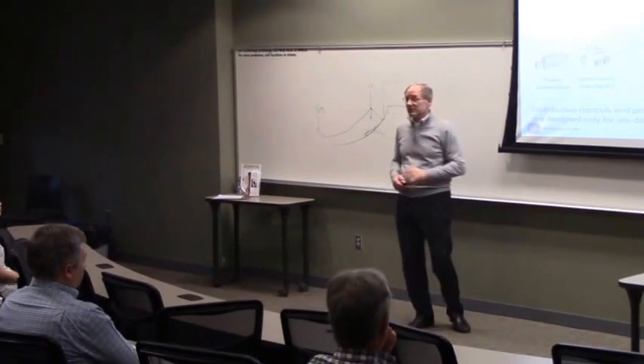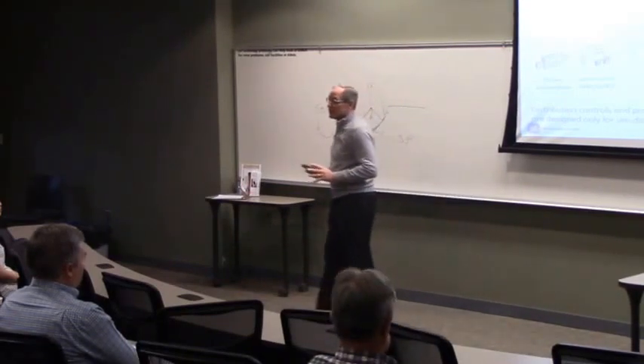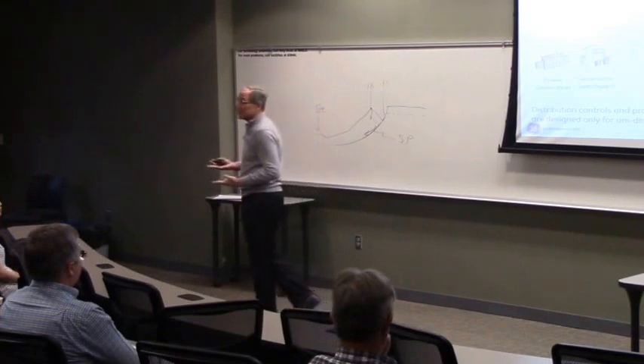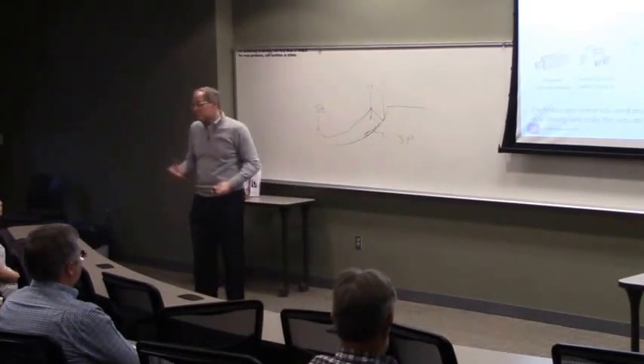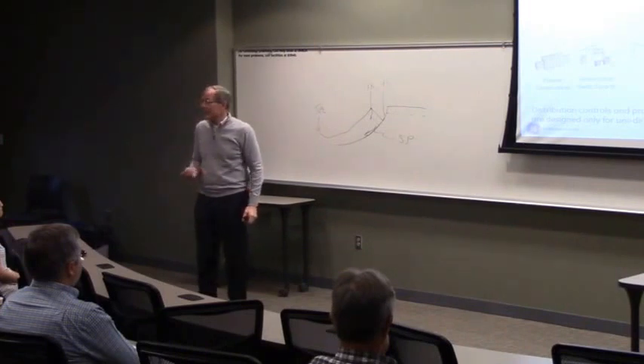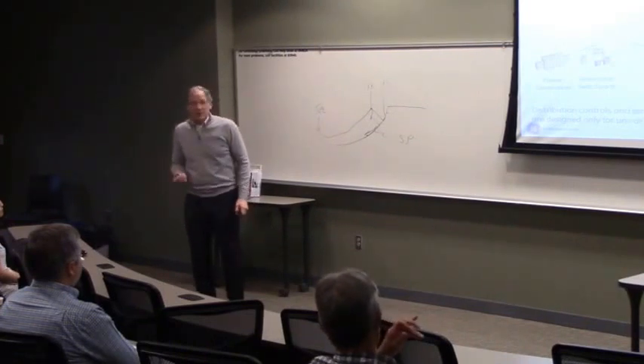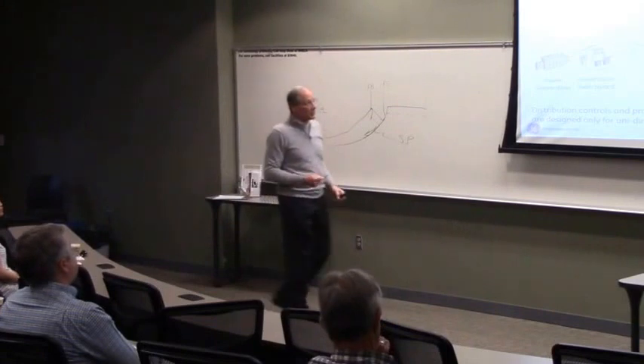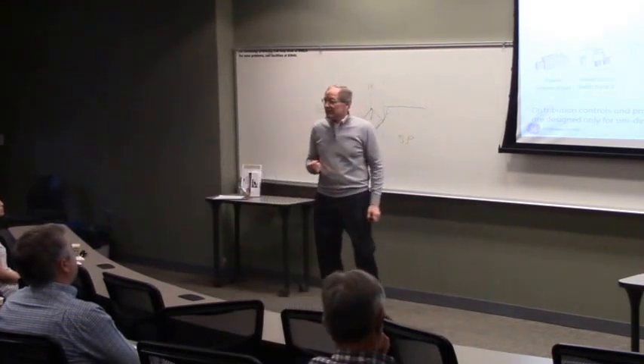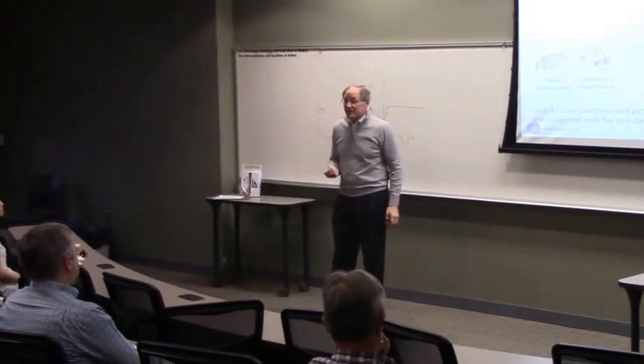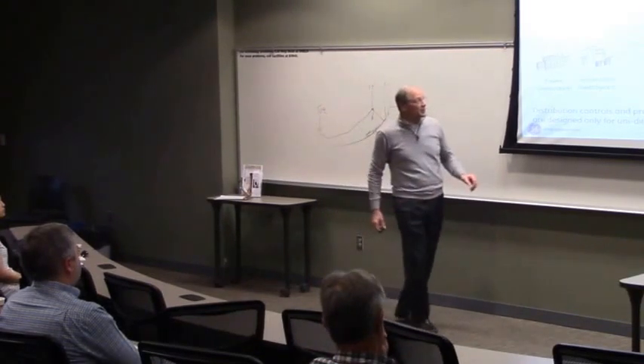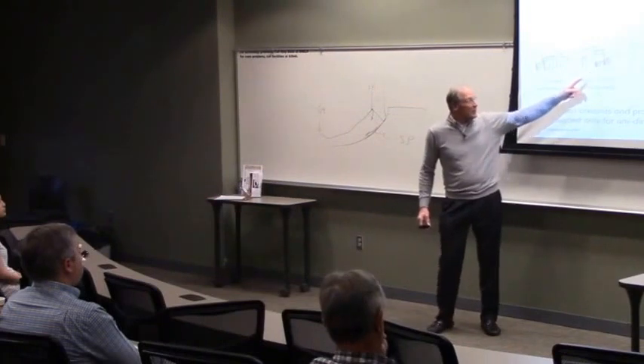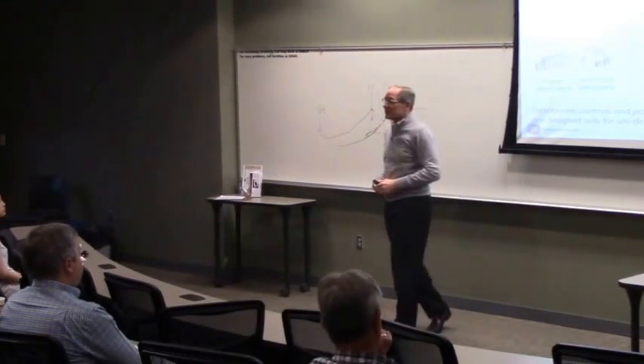Some of your output. So a generator step-up, a GSU, usually has more. We have different levels of transformer monitoring that we can provide, from a simple unit which looks at pressures, temperatures, and maybe one or two gases dissolved in the oil, to the ultimate, which would be a unit that can detect up to 9 different gases dissolved in the oil in the main tank of the transformer. So you find more investment in the transformer M&D devices on the generator step-ups.